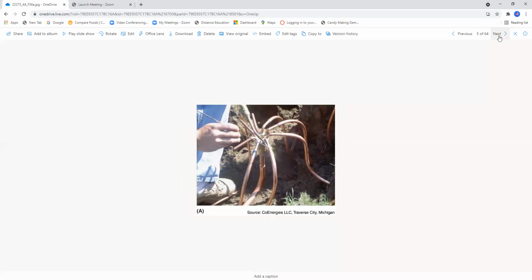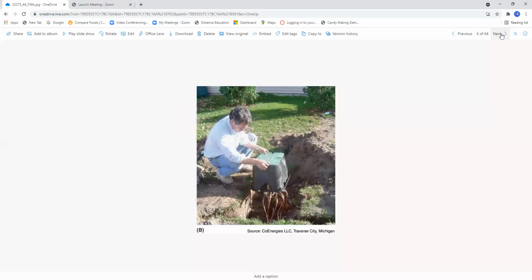Okay, here in figure 44.36, a copper header is being brazed to the supply and return loops by a technician. So obviously we're utilizing copper, but the copper inside the ground has no joints. So all your copper loops are going to be seamless in one piece. You will not have joints in the ground, in the burial of this type of copper. Okay, this appears to be a water box. In this particular case, it's a header box being positioned over the copper header. So basically you would install something like a sprinkler box over these brazed joints in order to gain access to it in the event that you have issues with this loop system.